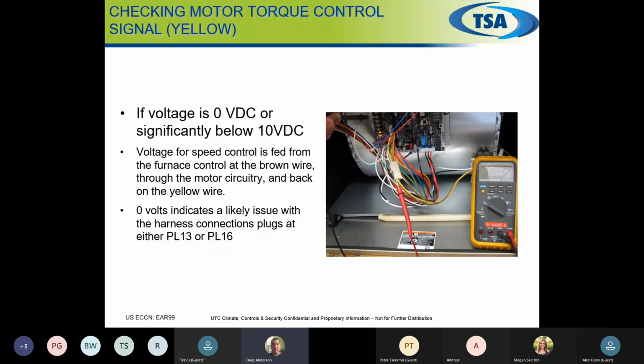Now we've tested our yellow. If we don't have voltage, or if we're under that 10 to 12, then we're looking at an issue before we even start. Same as if we don't have the 15 volts on the brown going to the motor. If we don't have that, or it's significantly under 10, then we have something going on with the power going into the motor.